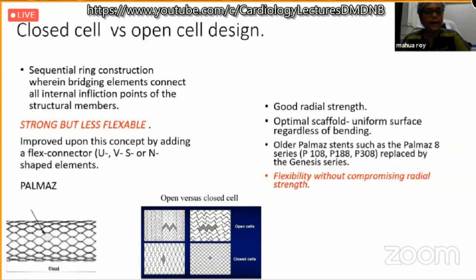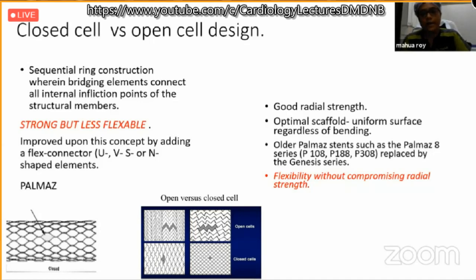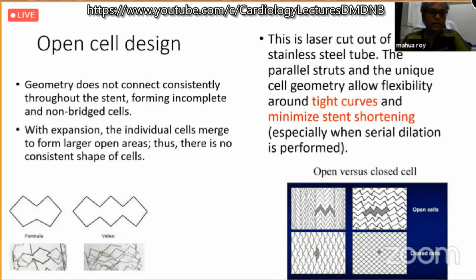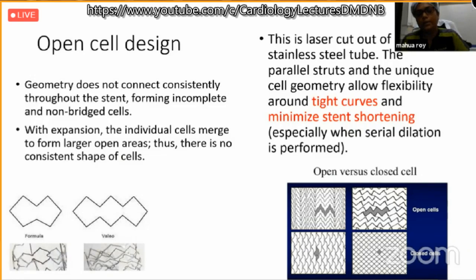Regarding cell design: closed-cell means the corner of a cell is attached to the neighboring cell, giving good radial strength but less flexibility. Some stents have designer modifications to improve flexibility without compromising radial strength. Open-cell design means the geometry does not connect consistently throughout the stent, forming incomplete or non-bridged cells. Open-cell design diminishes foreshortening, and when dealing with a curved structure the stent can conform to that curve.